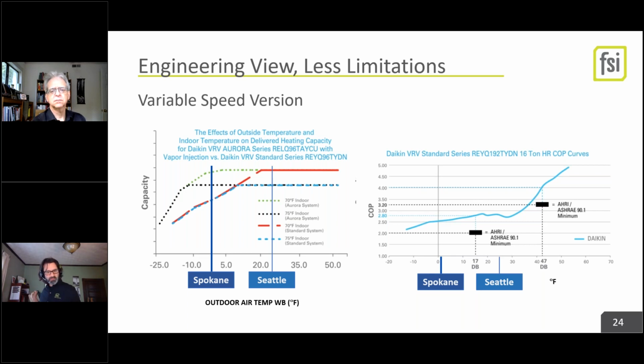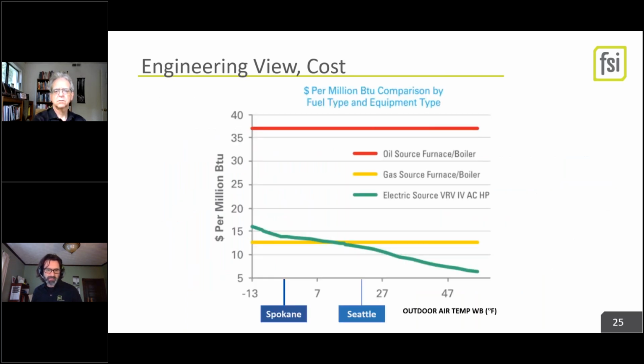The systems of 5 and particularly further back years ago, even with the variable speed compressors, you started to see a capacity drop certainly in Spokane, but even in Seattle, you might lose the top 10% on the coldest day of the year. Yeah, but VRF has really brought inverter-driven compressors, variable speed compressors.